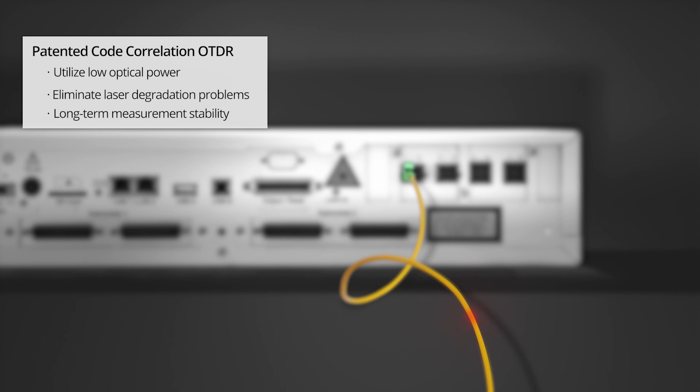through a single optical fiber. Light is scattered back, carrying temperature information along the route. The exact position of the temperature reading is determined by the arrival time of the returning light pulse.